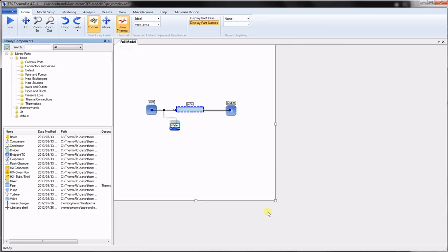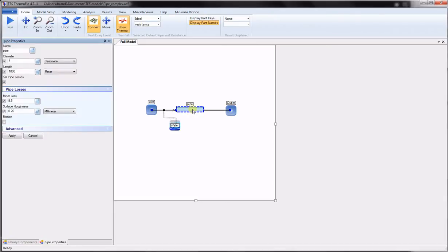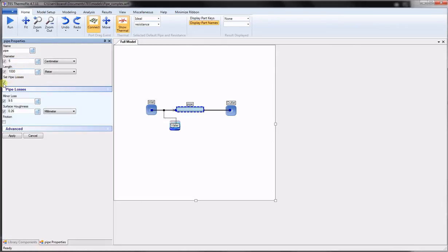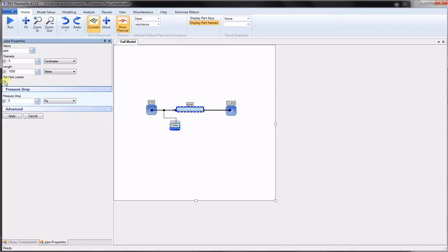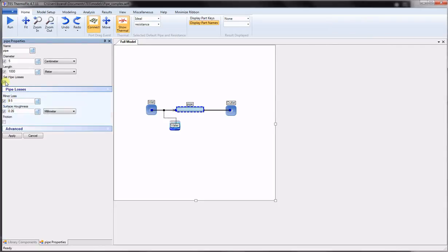The pipe component is the ideal tool for studying internal flows in pipes and ducts. The pipe's property form allows the user to enter any set of known pipe parameters and solve for the unknowns. You can set the diameter, length, and the pipe pressure drop using all losses including the minor losses and the friction factor either directly or using the surface roughness value. Alternatively, the user can solve for the pressure drop and any of these losses or set the pressure drop directly using this option.